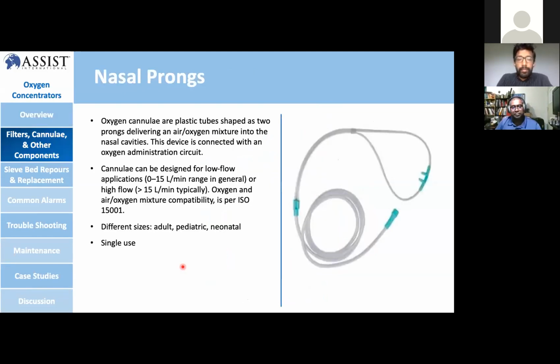A type of accessory that you're normally going to see is the cannula type, which you have to remember. You can use it in low flow applications, 0 to 15 liters per minute supply. And always remember, there are different sizes for adult and other units. Very important, it's single use. During COVID it's always single use, because the chance of transmitting infection will be much higher if you wrongly use it for another person. But remember, these are single use accessories.